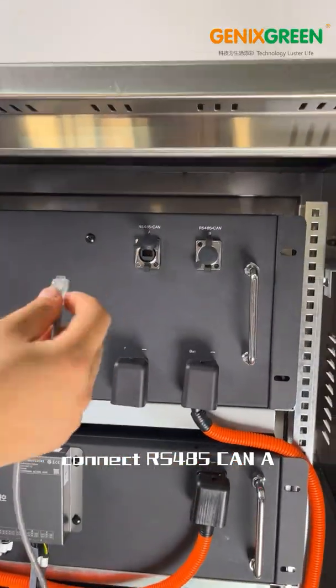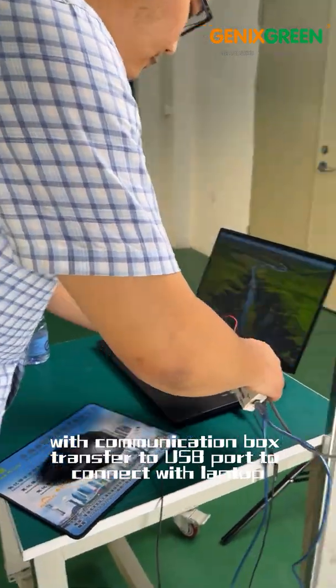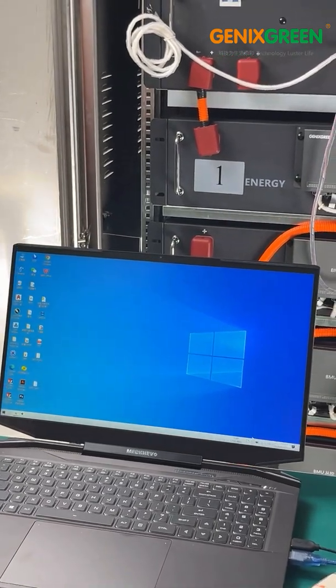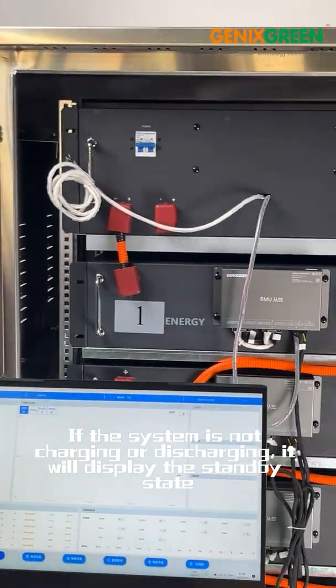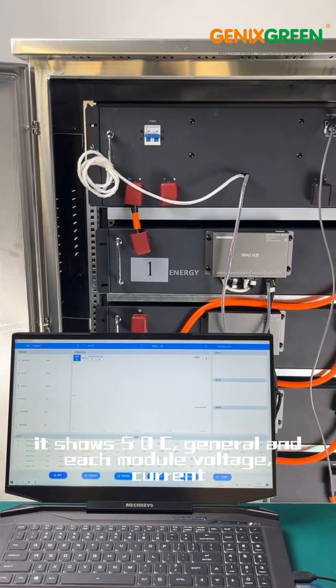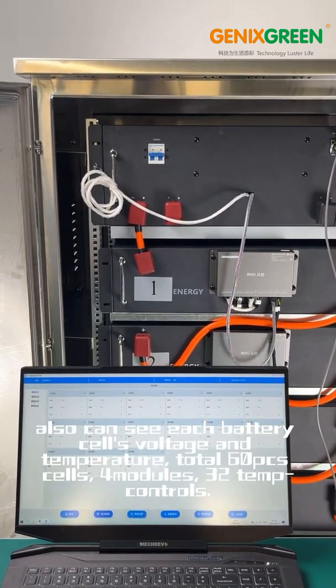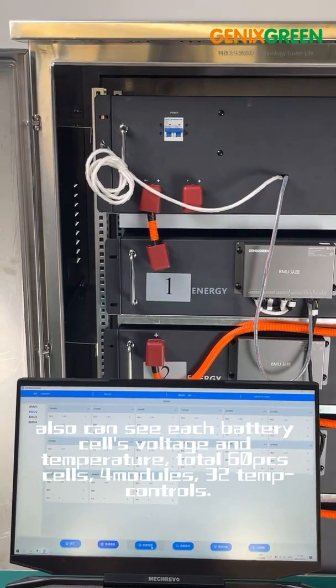Connect the RS485 to a communication box adapter to a USB port to connect with a laptop. Open the upper software. If the system is not charging or discharging, it will display the standby state. It shows SOC, general and each module voltage, and current. There are port alarms for first, second, and third levels. You can also see each individual cell voltage and temperature. Total: 60 cells, 4 modules, 32 temp controls.